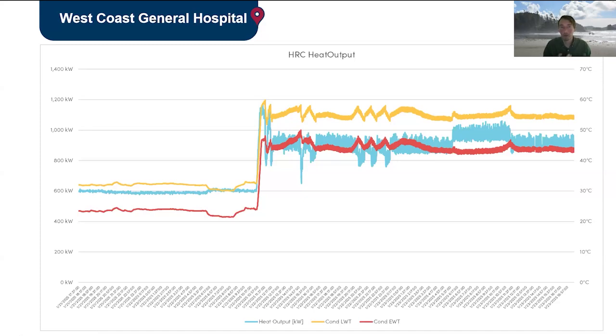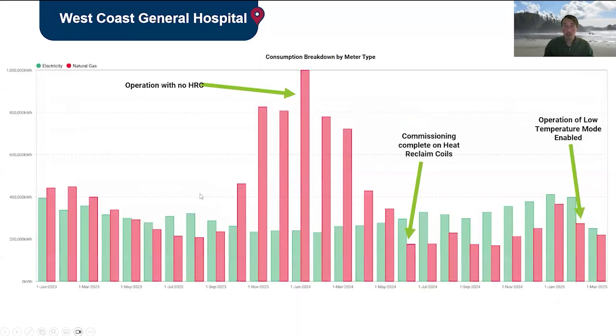So just really rough math, that's almost a 50% boost of capacity. And if you go to the next slide, you can see that in order to implement those heat reclaim coils, we had to shut down our heat recovery system. Unfortunately, it took a very long time. The red bars here show almost a full winter without operation of our heat recovery chiller system, because that's how long the system was down in order to enable this.